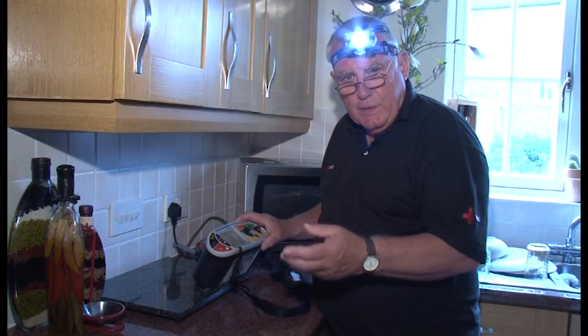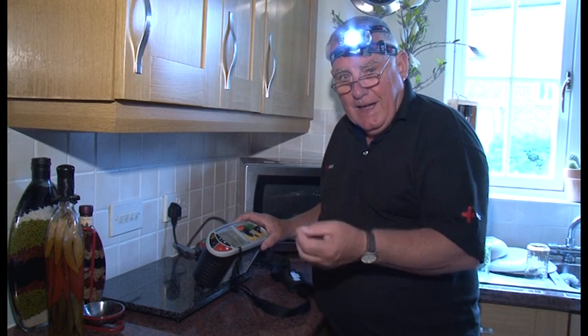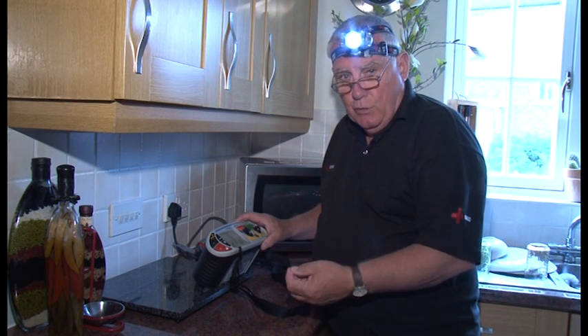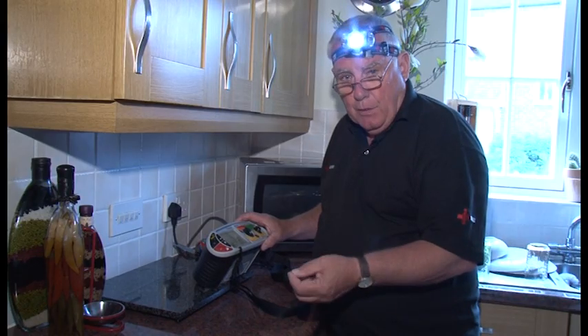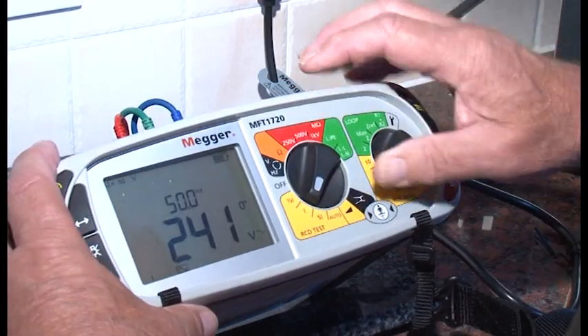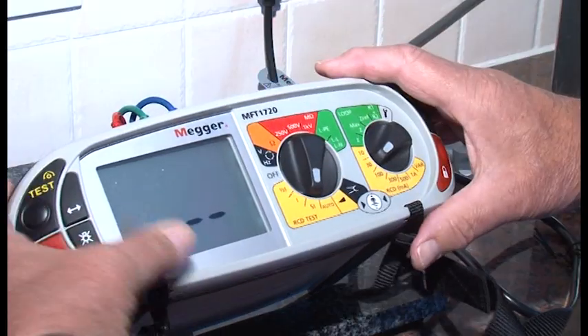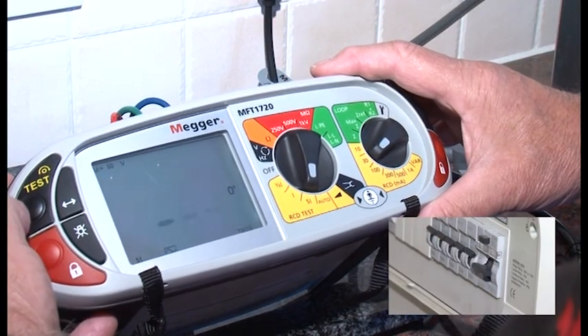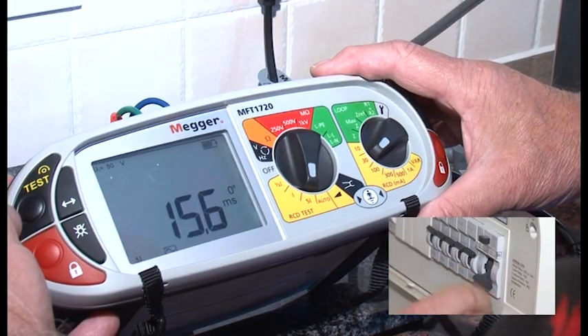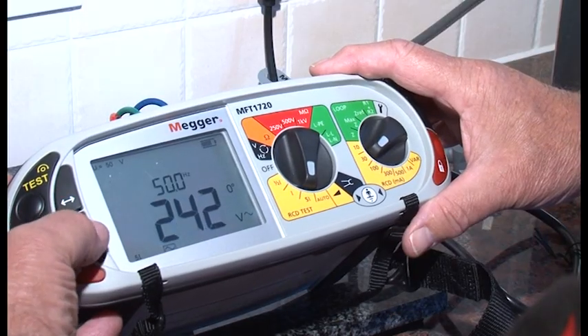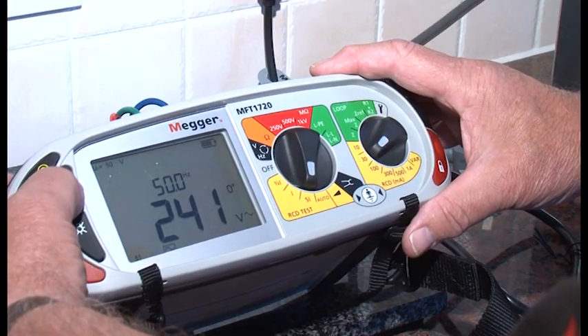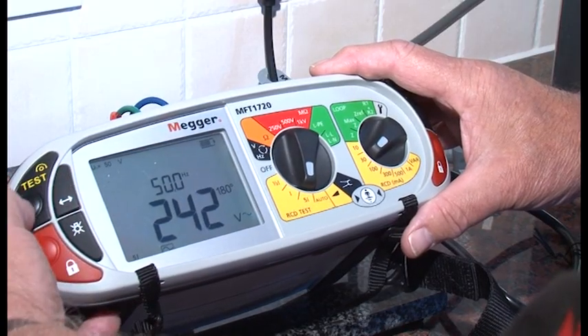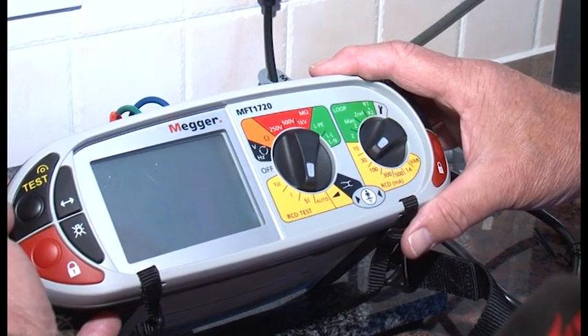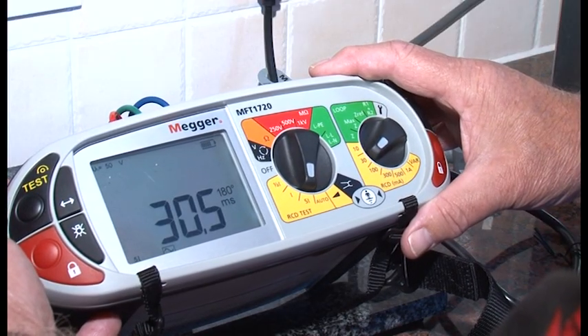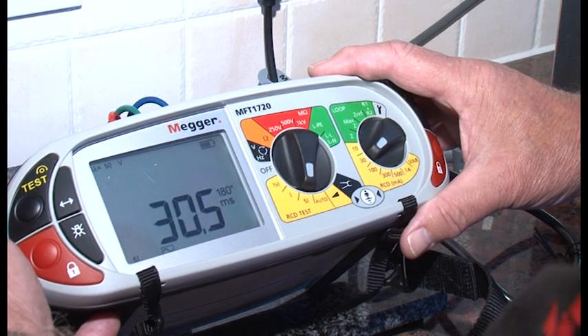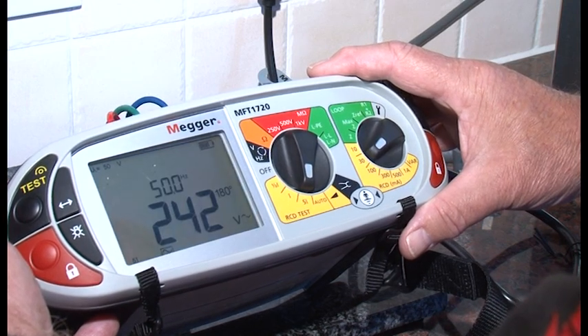For the second test, we select 5 times the rated current. And here, an RCD provided for additional protection against electric shock must operate within 40 milliseconds. So I'm going to change it to 5 times. Press the test button. And then you can see I've got a reading of 15.6 milliseconds. Now I'm going to change the waveform. Press the test button. And I've got a reading of 30.5 milliseconds. And that will be the reading that I will record.